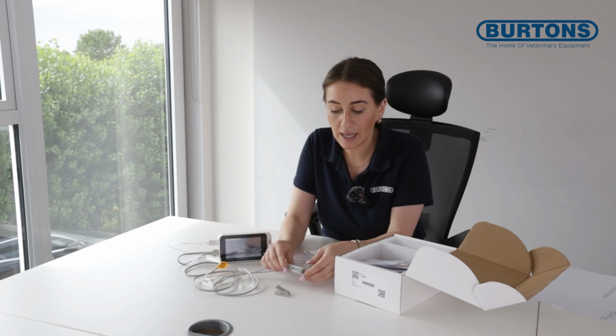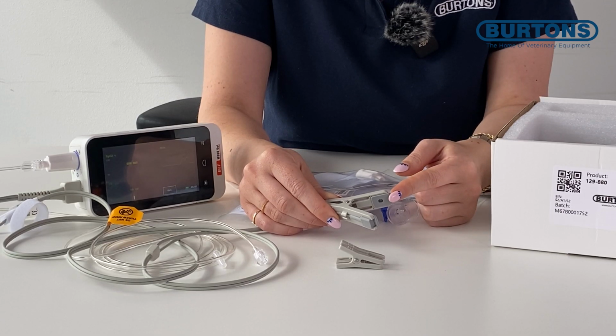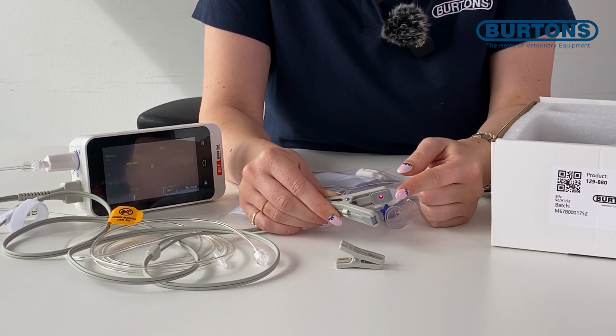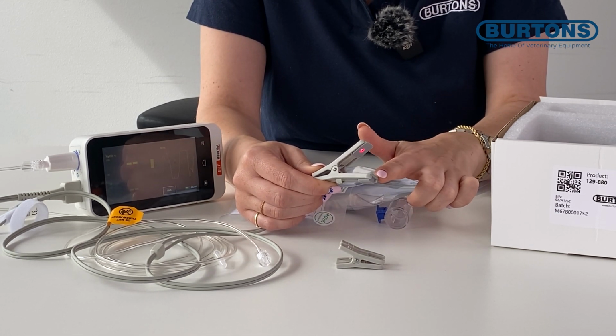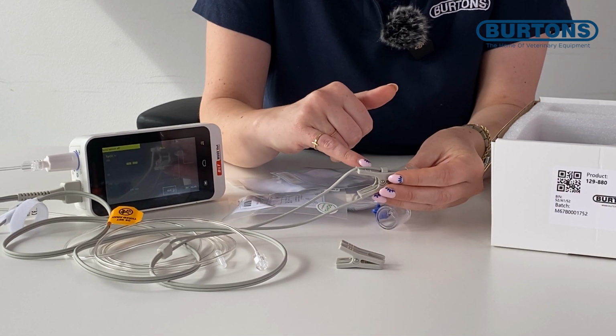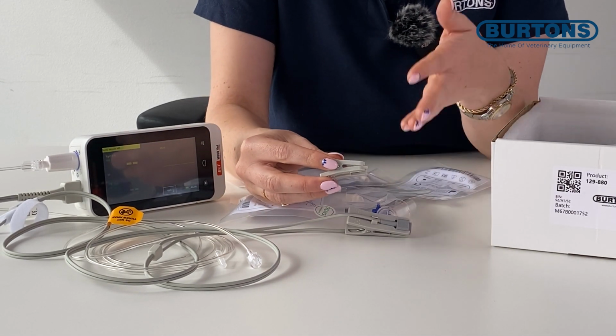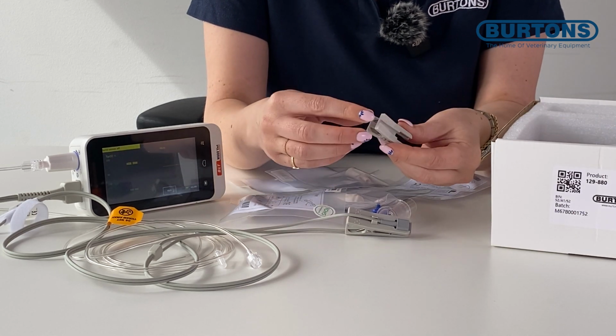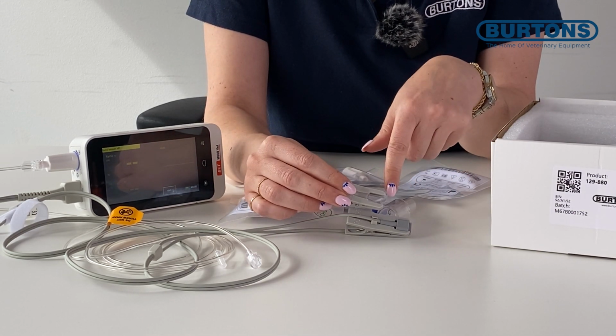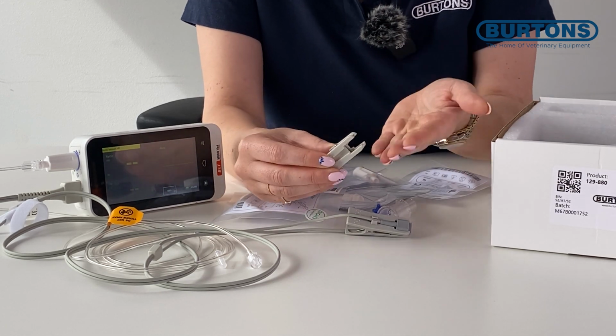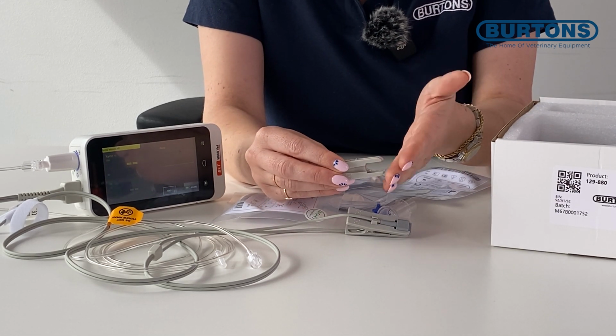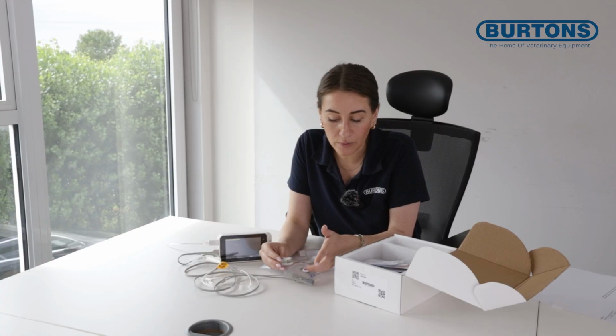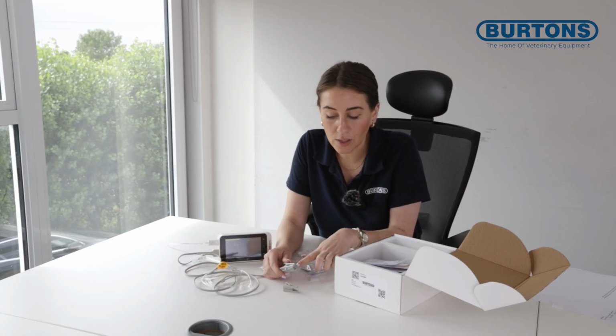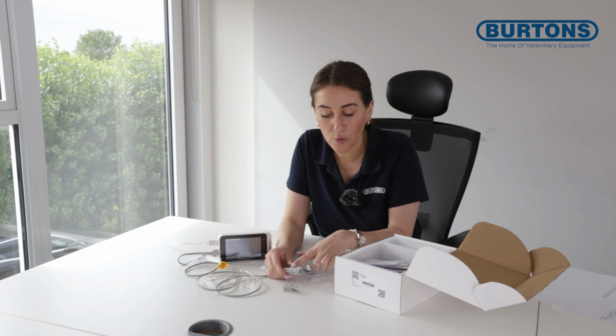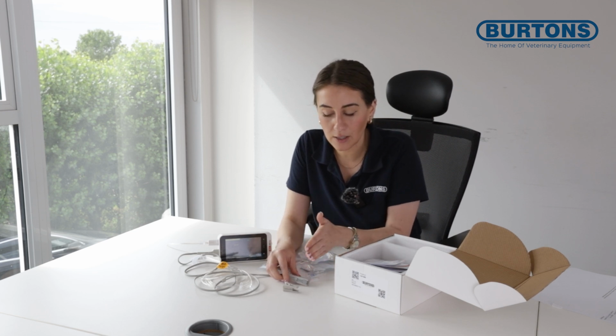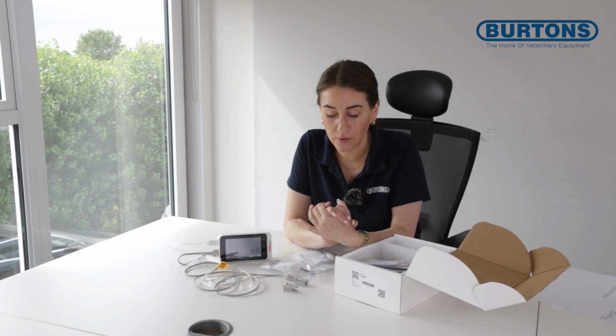In terms of cleaning the sensor itself, it's recommended that we use 70% isopropyl alcohol on a lint-free cloth to clean both the infrared light and the receiver. Very often you'll get blood into the probes itself if the patient's having, let's say for example, a dental surgery or facial surgery, and these come away, as you can see from here, and they can be swapped out. So then you can use let's say a harsher cleaning agent like your hospital grade detergent to remove any debris or blood that gets inside the probes themselves. But it's really important to separate the sensor from the probe so that you can clean them adequately with the different agents that you need to use for them.